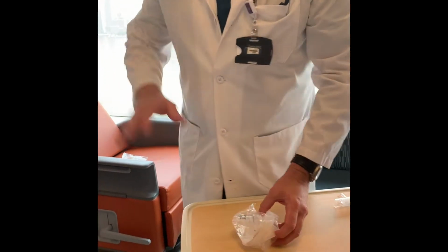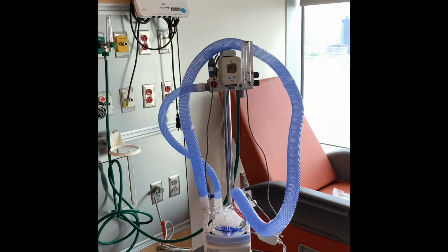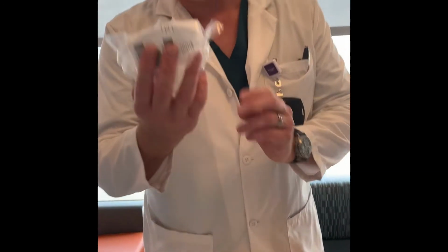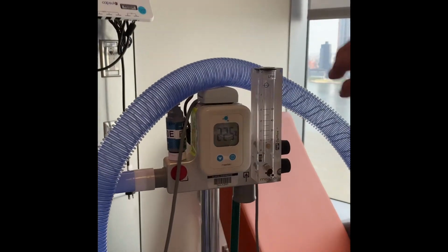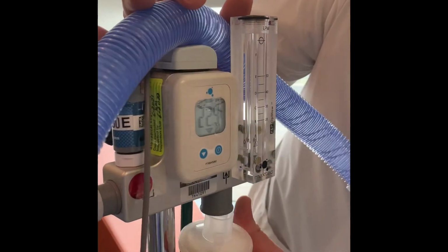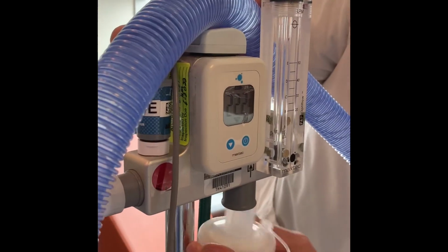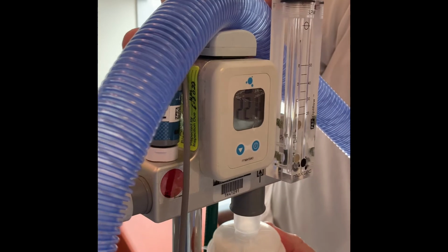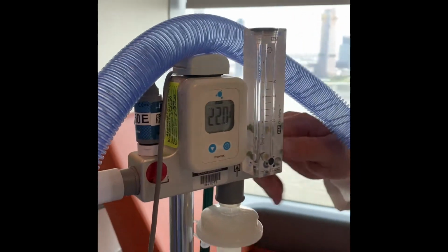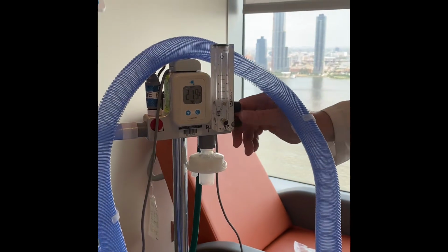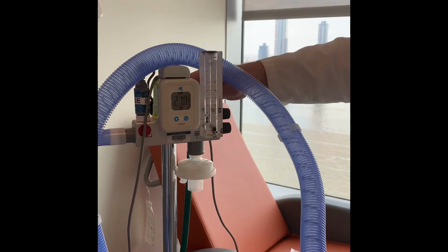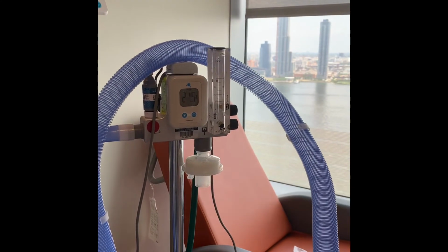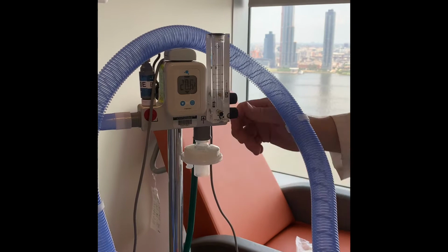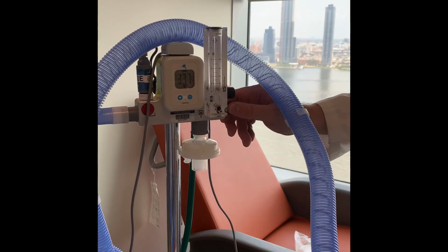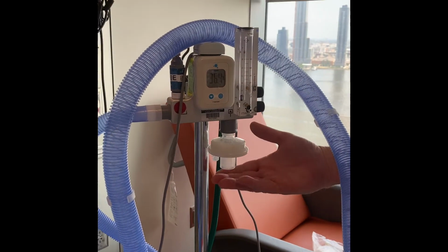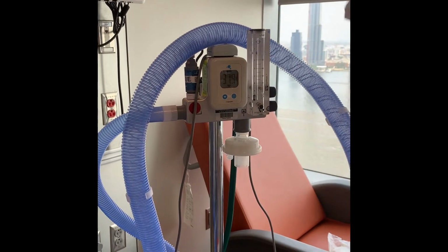In addition to all the other equipment, as an added safety precaution, we use a HEPA filter. And this HEPA filter goes in the entrainment port. So right under here, there's a hole and it fits right in. And what it does is, when you entrain the air, two things it does actually. It quiets the machine down a lot, it's almost like a muffler, and it filters the air that's going to the patient.